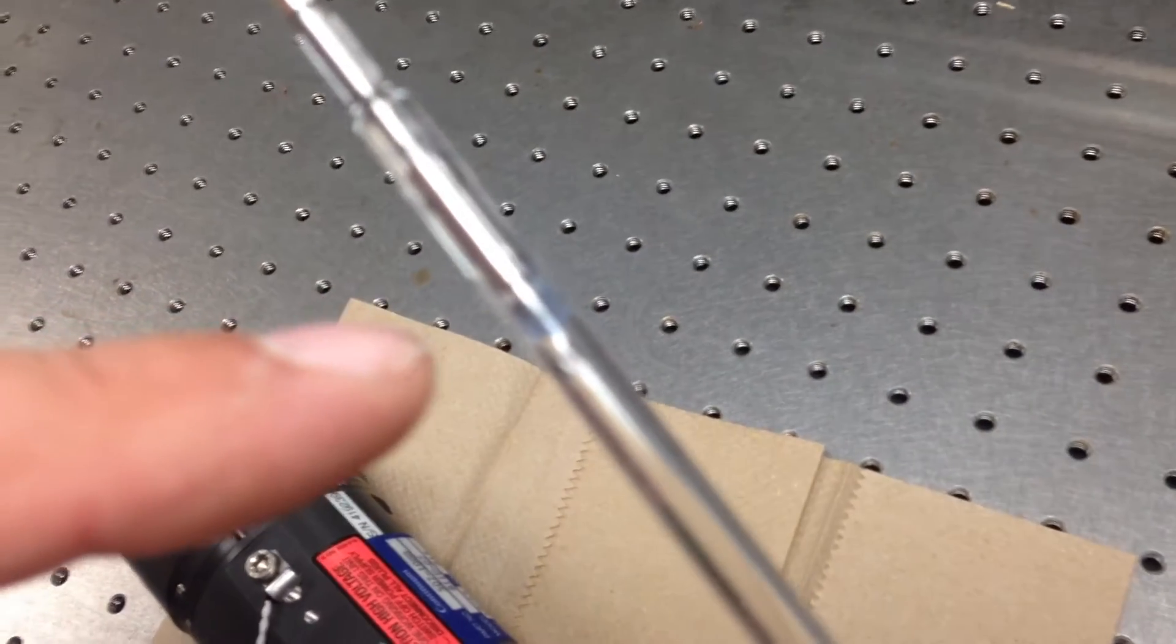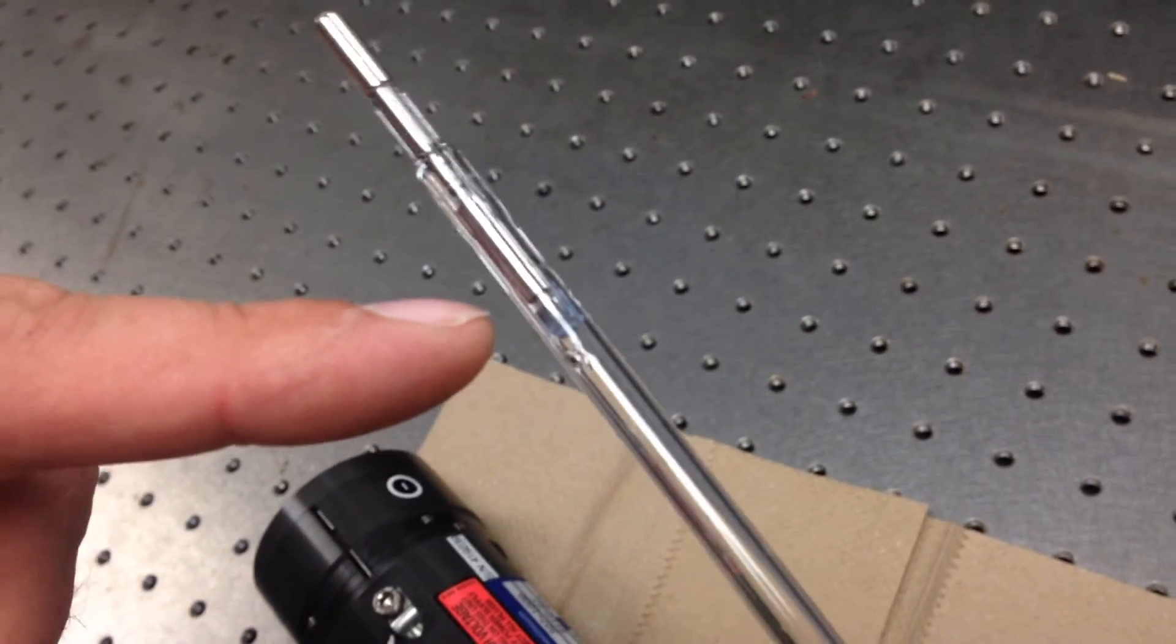Now you may note right in here there is a little bit of white sputtering that is starting to occur on the lamp. As the lamp ages it will start migrating from the negative end towards the center. And that's how you kind of note the degradation of the lamp. It's just barely starting to happen there.